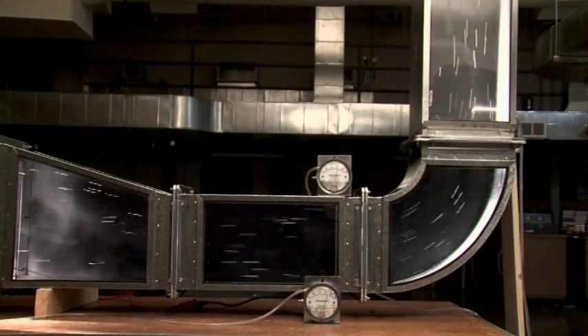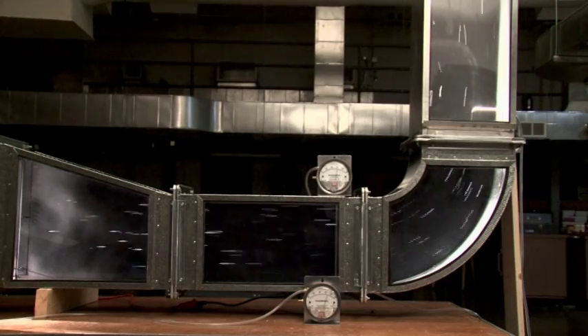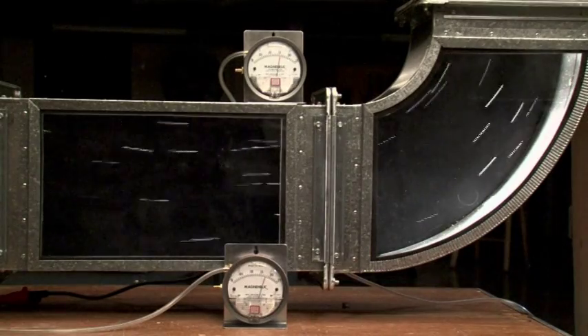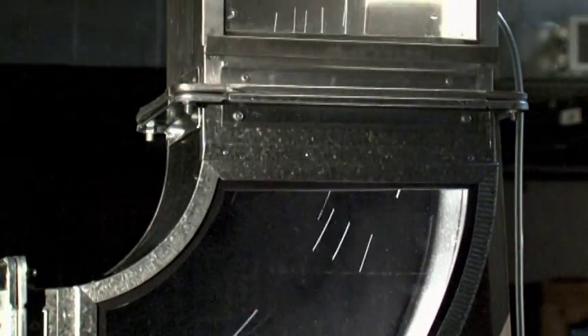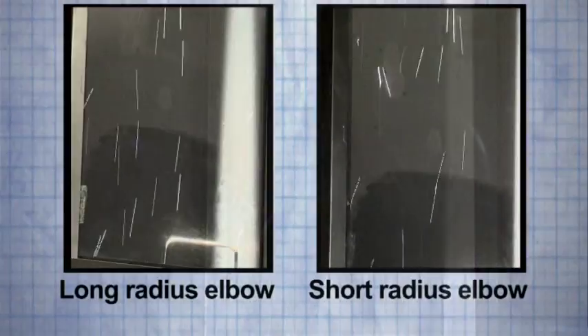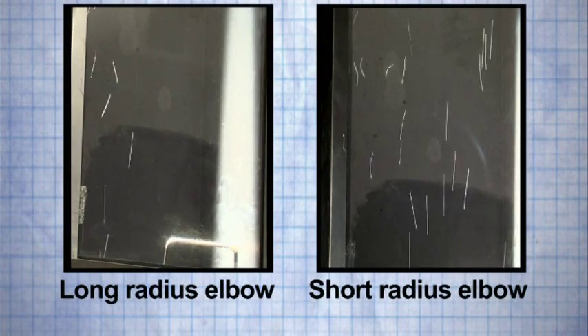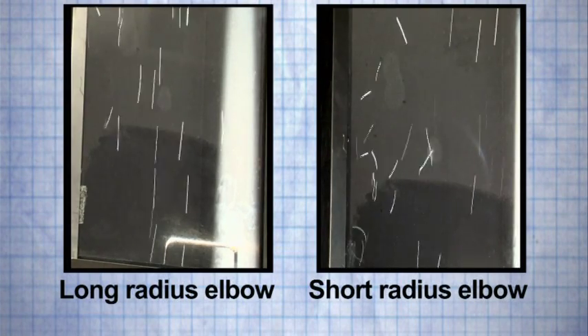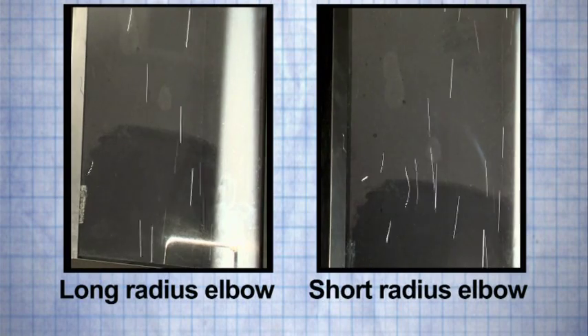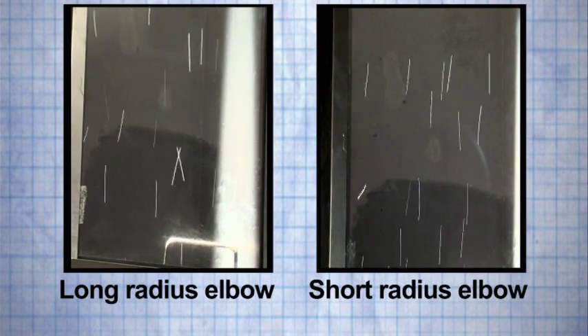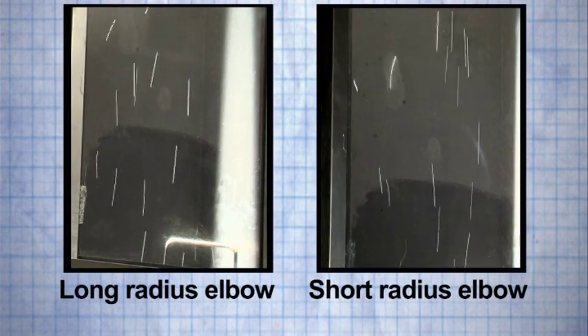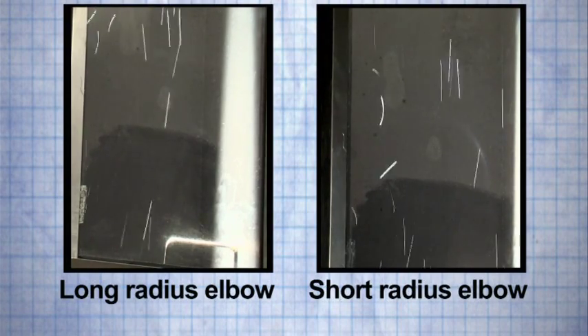This wide shot shows the same reducer and straight duct section, but this time a short radius elbow is used to turn the airstream 90 degrees into the branch duct. While both radius elbows display similar flow characteristics, a difference is discernible in the downstream air turbulence when the two are shown side by side. Typically, the longer the turning radius, the lower the pressure loss. The trade-off is that the cost to construct increases as the elbow's radius increases, and more space is required as the fitting's radius increases.